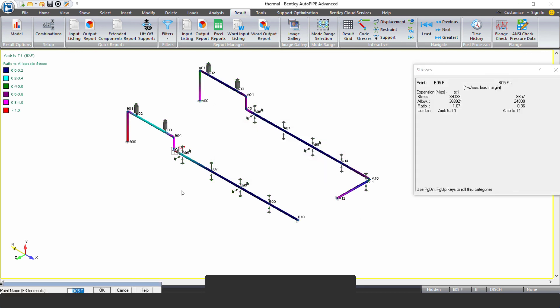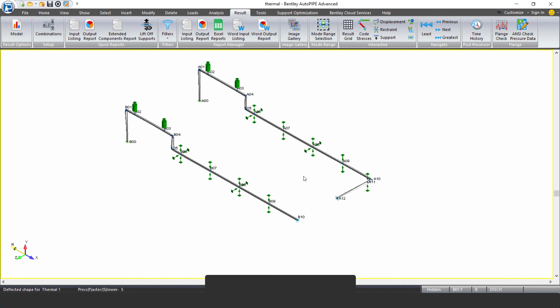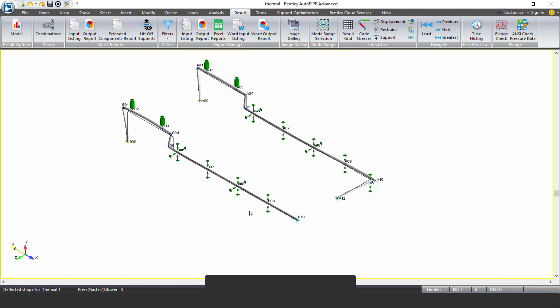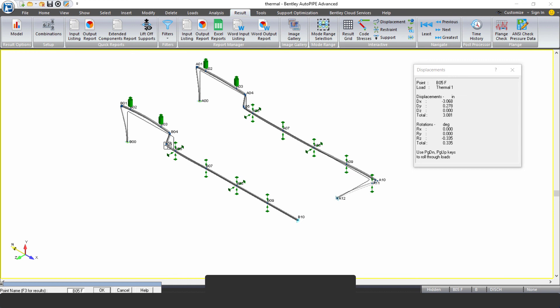So if we run the analysis again and we review our stress results, we'll do it for thermal. We now see that we have the red means that we're over a ratio of one. So we're overstressed. So let's look at the displacement plot for thermal. We can animate it. And we see that this looks similar because we have a similar thing going on. But this ability for this pipe to grow in this direction is now gone. It's just stopped there. It's a rigid anchor. So that's what's causing that overstressing there. So what can we do?